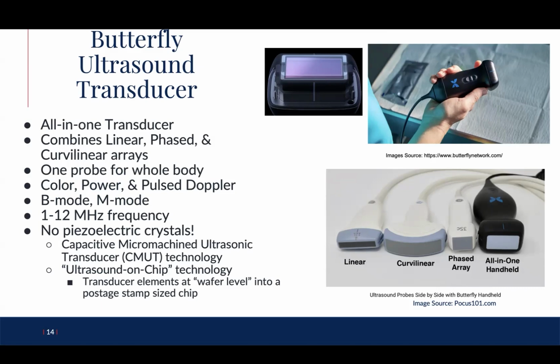This probe differs from standard probes by not containing piezoelectric crystals. Instead, the probe has an ultrasound on-chip technology through a capacitive micro-machined ultrasonic transducer, where the elements are in a chip roughly the size of a postage stamp. And as you can see in the picture on the lower right-hand corner, it combines all of this in one handheld device.